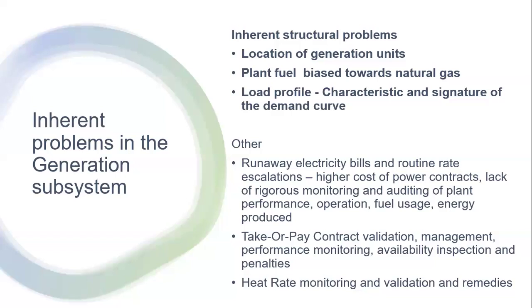The other thing is heat rate curves for generators, right? We need to validate them to make sure, especially from the Energy Commission, who gives the licenses for power plants, before any power plant goes in for application or gets built. From my experience, they'll have to declare their production capability, and that is in the form of heat rate curves. We do production simulations to see if indeed they are capable of what they say they are.